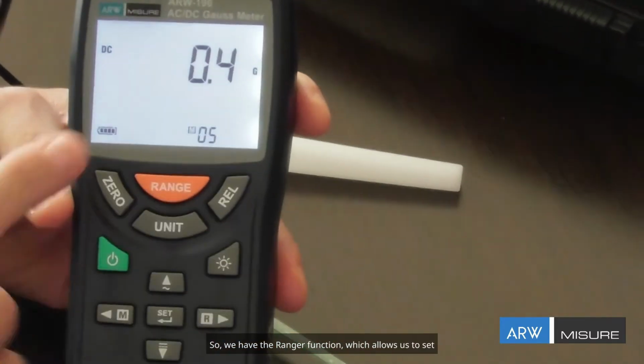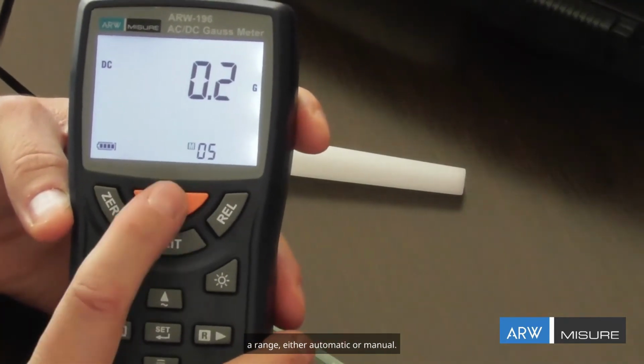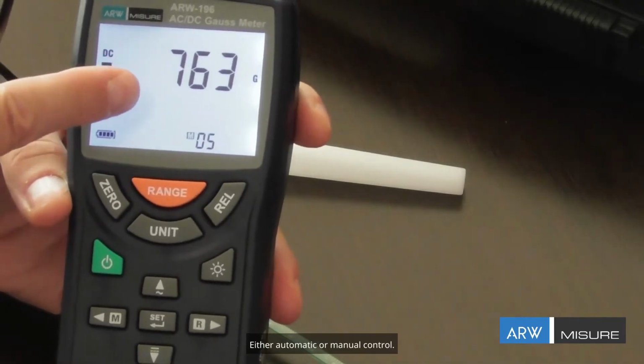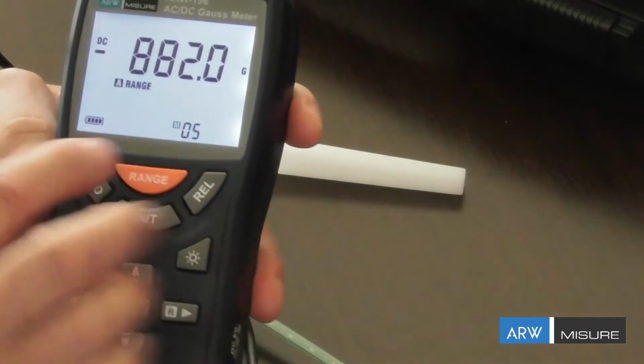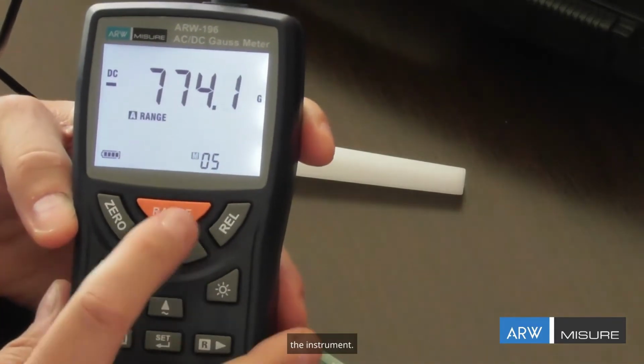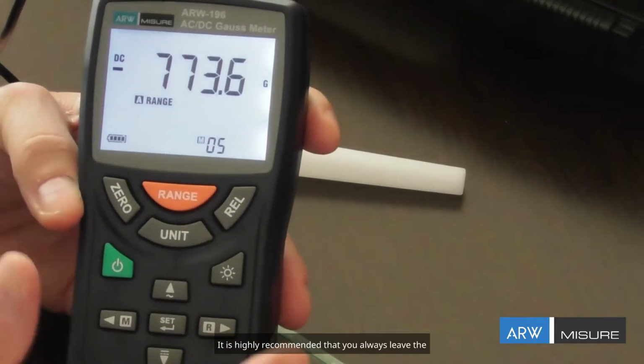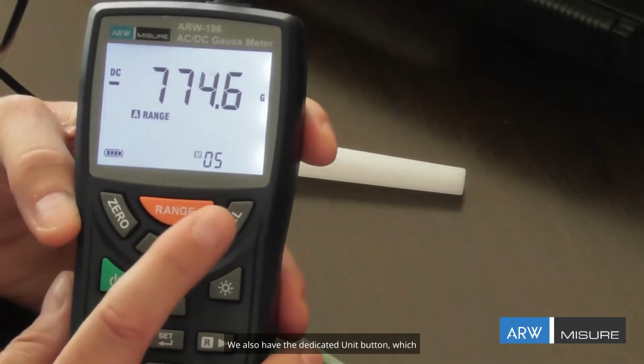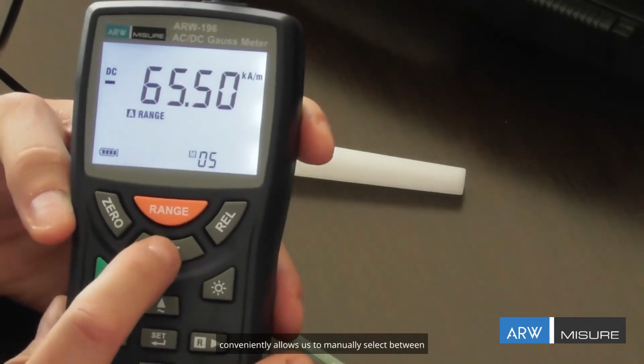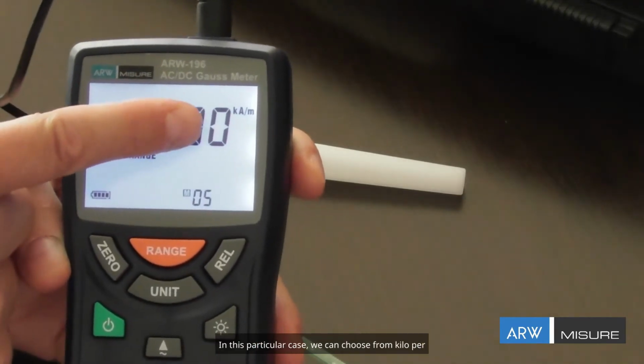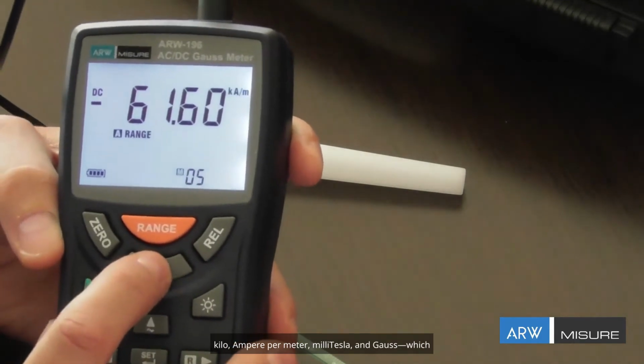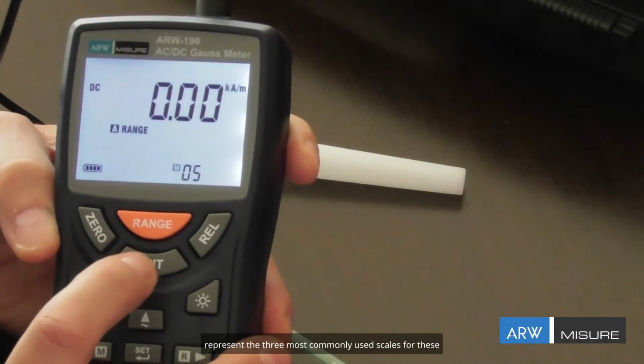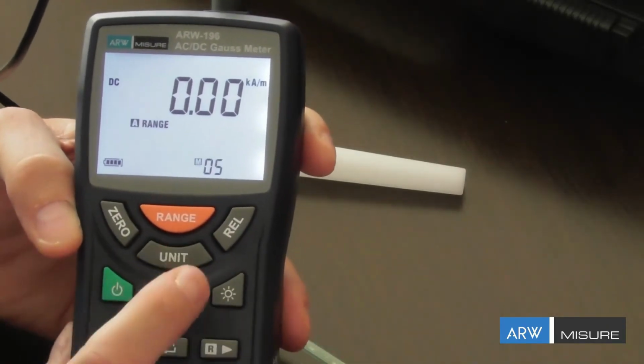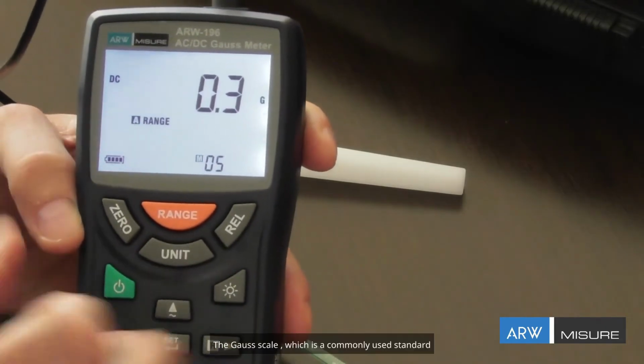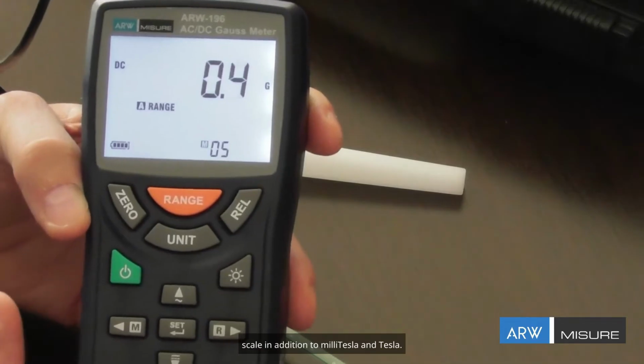Let's take a look at the various functions. So, we have the range function, which allows us to set a range, either automatic or manual. Clearly, this significantly changes the resolution of the instrument. It is highly recommended that you always leave the device set to the auto range mode for optimal performance. We also have the dedicated unit button, which conveniently allows us to manually select between several different measurement scales. In this particular case, we can choose from kiloampere per meter, millitesla, and Gauss, which represent the three most commonly used scales for these types of magnetic readings. The Gauss scale, which is a commonly used standard scale in addition to millitesla and Tesla.